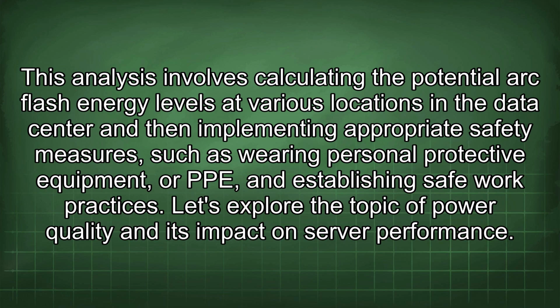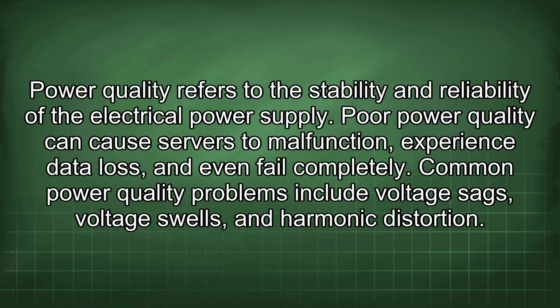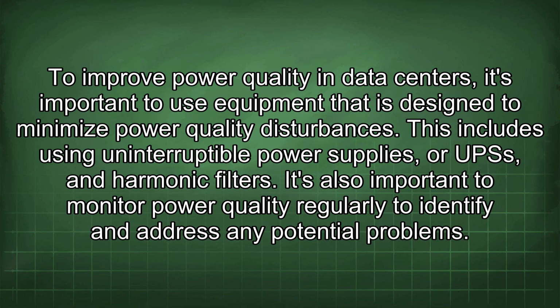Let's explore the topic of power quality and its impact on server performance. Power quality refers to the stability and reliability of the electrical power supply. Poor power quality can cause servers to malfunction, experience data loss, and even fail completely. Common power quality problems include voltage sags, voltage swells, and harmonic distortion. To improve power quality in data centers, it's important to use equipment that is designed to minimize power quality disturbances. This includes using uninterruptible power supplies, or UPSs, and harmonic filters. It's also important to monitor power quality regularly to identify and address any potential problems.